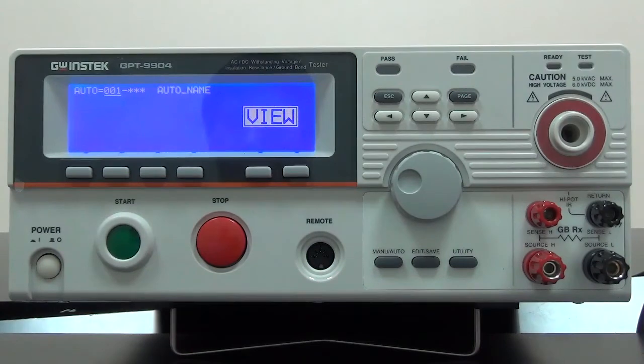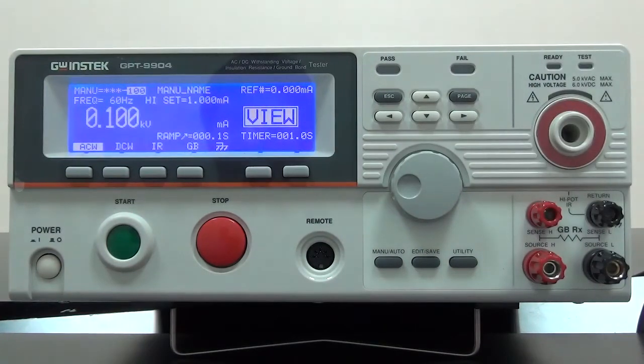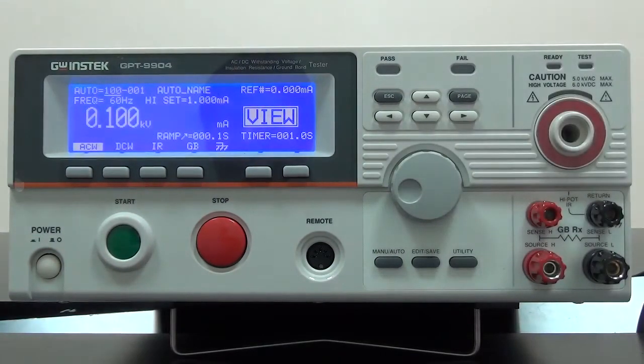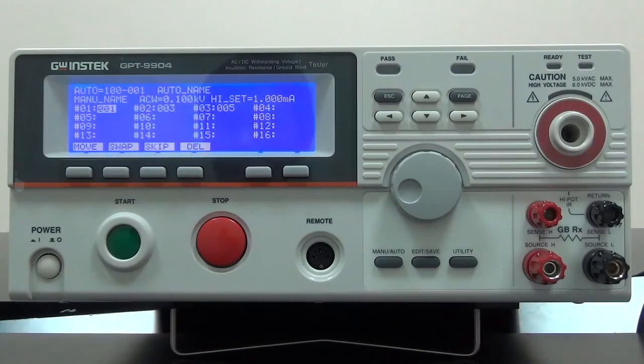MANU is to set individual test condition, and there are 100 sets total. Auto is to combine preset MANU conditions as a sequential group for execution, and there are also 100 sets. By pressing the page key, we can see that each group can maximally combine 16 MANU conditions.